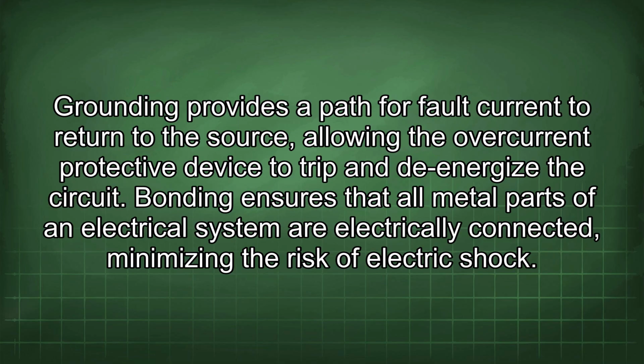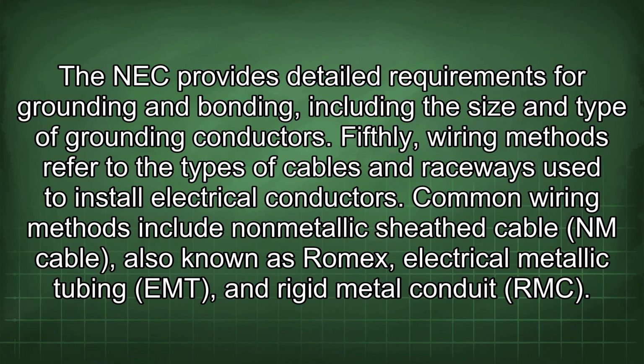Fourthly, grounding and bonding are essential for electrical safety. Grounding provides a path for fault current to return to the source, allowing the overcurrent protective device to trip and de-energize the circuit. Bonding ensures that all metal parts of an electrical system are electrically connected, minimizing the risk of electric shock. The NEC provides detailed requirements for grounding and bonding, including the size and type of grounding conductors.